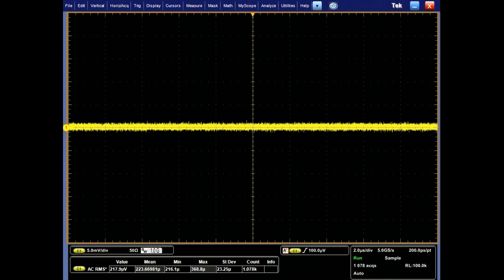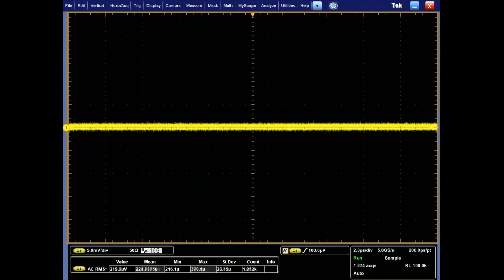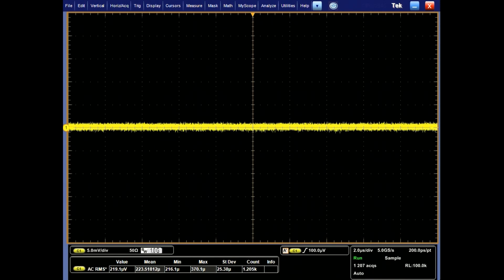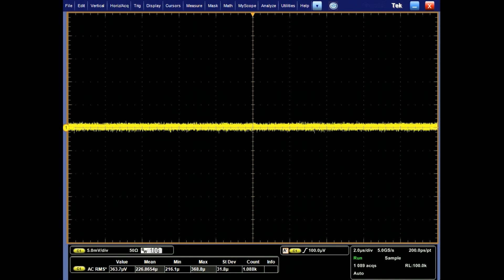A previous generation scope at one gigahertz bandwidth with five millivolts per division vertical scale and no signal connected shows 217 microvolts of noise.